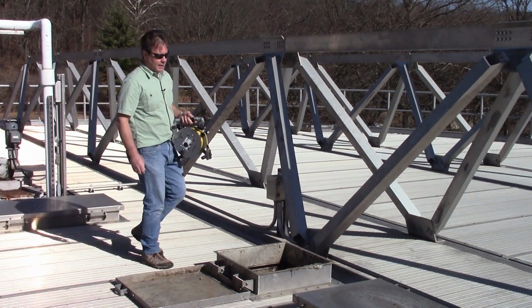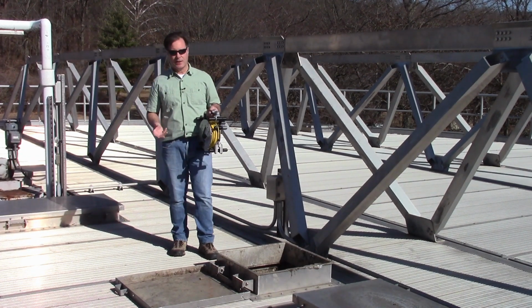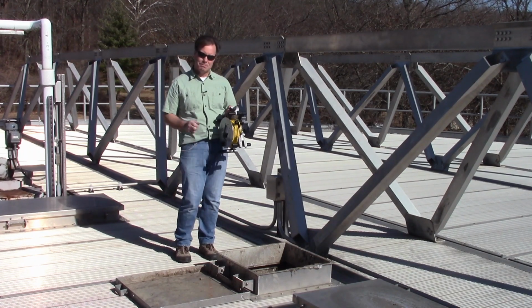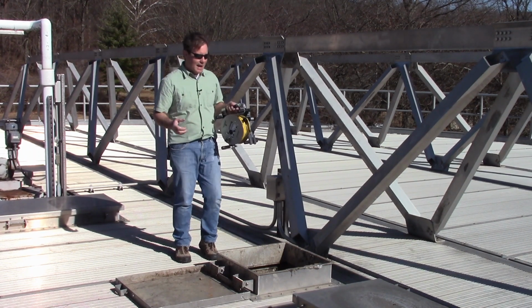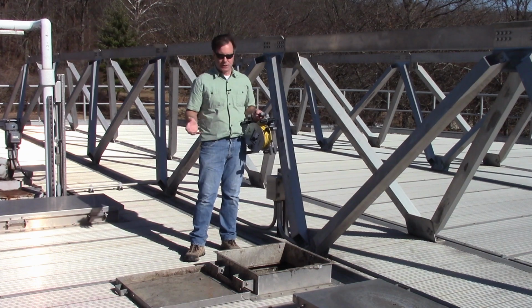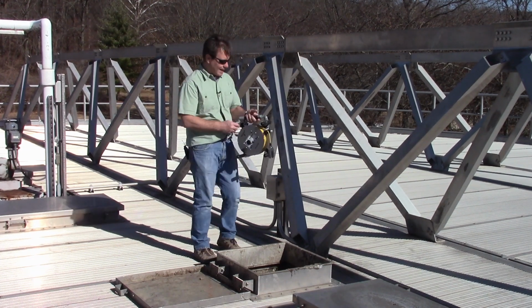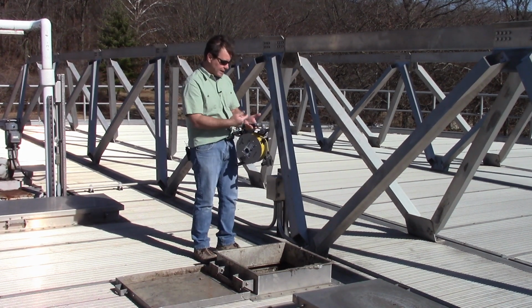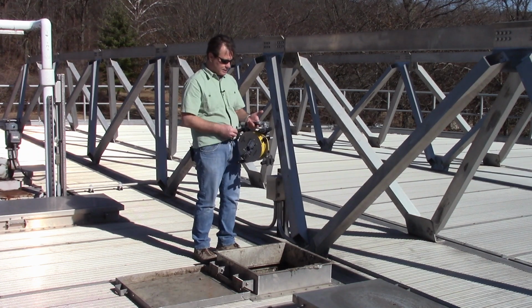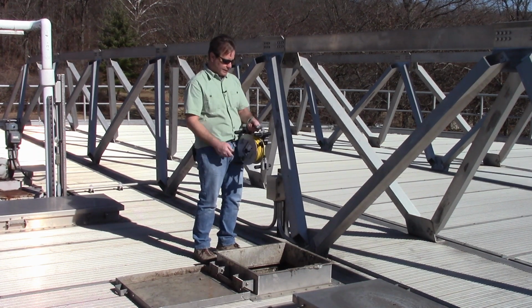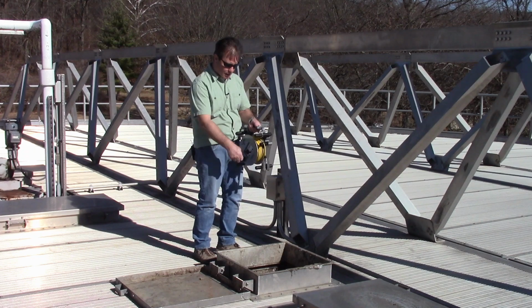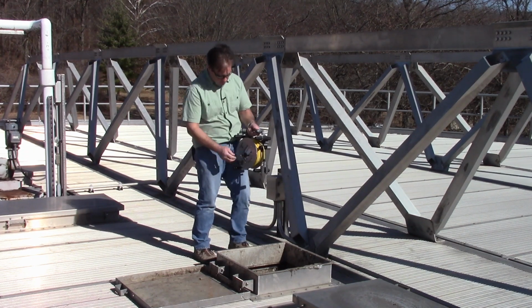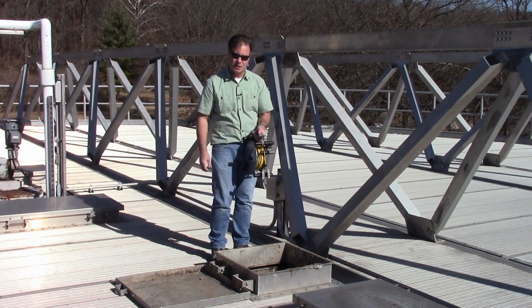Okay, we just saw how the SID Rotary is used on a secondary clarifier with the base station mounted on the railing. Now we're on top of a digester, and obviously no railings. So we have an optional accessory, which is this freestyle handle that's mounted on the existing bars. There's a lever to release the brake, which allows the operator to lower the probe to the bottom of the tank. So let's power this up and measure the sludge in this digester.